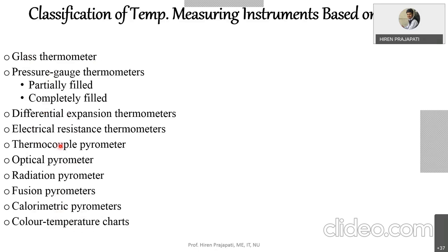Briefly on pyrometers: they are non-contact instruments. When you heat any material, its color changes, so an optical pyrometer works based on the change in color with temperature. A radiation pyrometer works based on radiation emitted from a hot body — every body emits radiation based on its temperature, and the radiation pyrometer measures temperature from that emitted radiation.